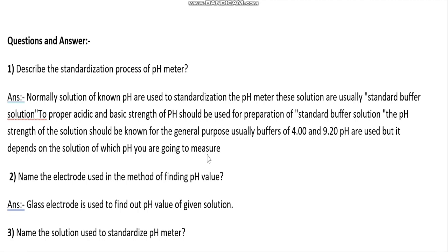Question and answer: describe the standardization process of pH meter. Normally, solutions of known pH are used for standardization of a pH meter; these solutions are usually standard buffer solutions. To properly represent acidic and basic strength, the pH should be known. For general purposes, buffers of pH 4 and 9.2 are used, but it depends on the solution whose pH you are going to measure.